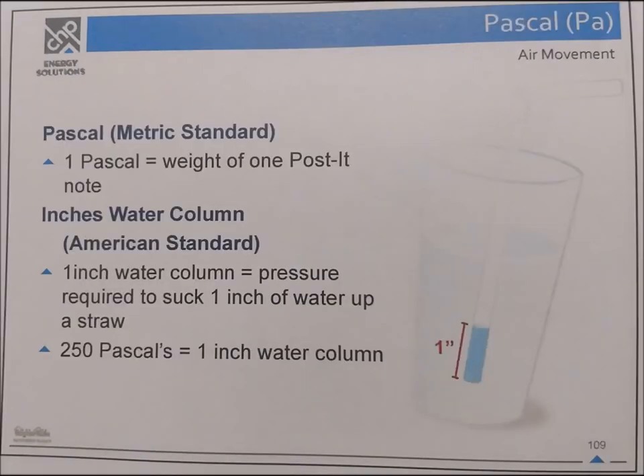Pascal (Pa) is the metric standard for air movement pressure. One pascal equals the weight of one Post-it note. Inches of water column is the American standard — one inch of water column equals the pressure required to suck one inch of water up a straw. 250 pascals equals one inch of water column.